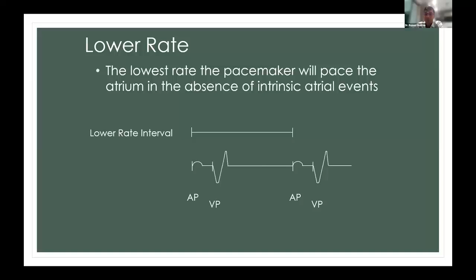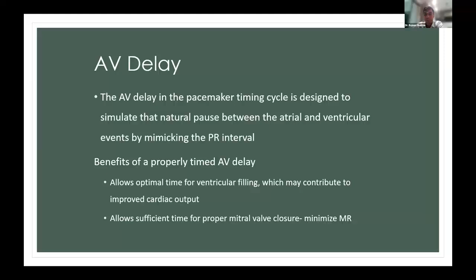Regarding AV delay, it is a pacemaker timing cycle designed to simulate the natural pause between the atrial and ventricular events by mimicking the normal PR interval seen in ECG. We have to program it properly because it allows optimal timing for ventricular filling, which may contribute to improved cardiac output, and allows sufficient time for proper mitral valve closure, so we minimize the diastolic MR. So the AV interval is initiated by a paced or non-refractory sensed atrial event. If it follows a paced event, it is called the paced AV interval. If it follows a sensed atrial event, it is called the sensed AV interval.